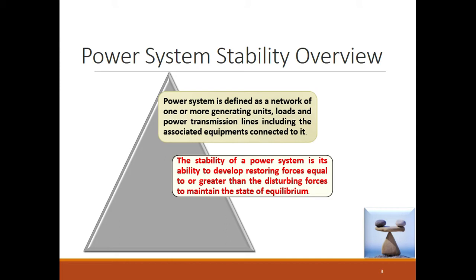Now suppose there is a 10 megawatt load increase on the power system. The output is now 110 megawatt, keeping losses constant at 20 megawatt, that is 130 megawatt total, whereas the input is 120 megawatt. Therefore there is an imbalance. The power system has to be capable of producing extra 10 megawatt so that input equals output plus losses again. That extra 10 megawatt the power system produces is what we call the restoring force.